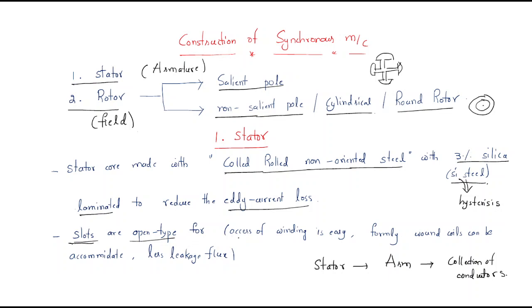The reason open type slots are used is: first, access of winding is easy; second, firmly wound coils can be accommodated; and third, leakage flux is less. These are the three reasons for using open type slots.